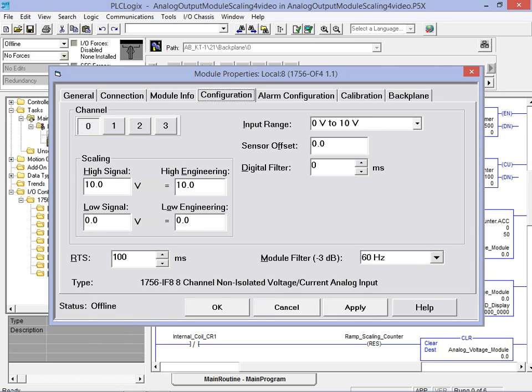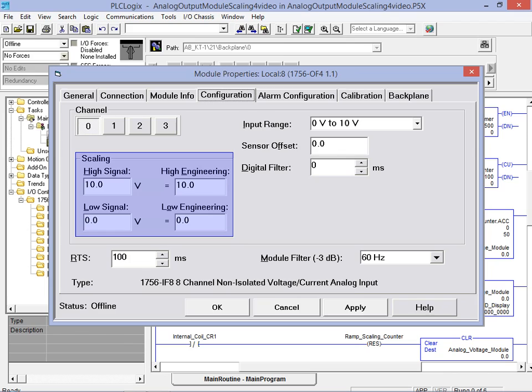We now move on to define the output scaling. The high and low signal values represent the actual voltage that will appear at the terminals of the channel 0 slot 8 output location. The high and low engineering values represent the value range that is being sent to that output location from the PLC application.